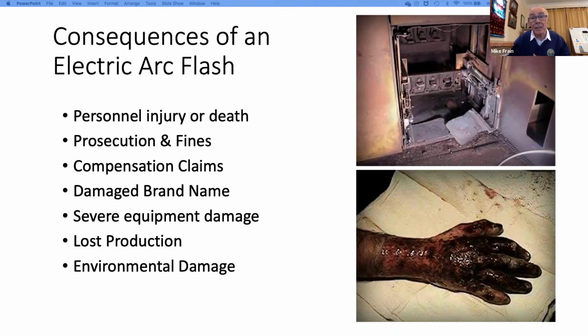Just recently, an electrical contractor here in the UK was fined £1 million plus costs for breaches of Section 2(1) of the Health and Safety at Work Act 1974. It followed burns to an electrician who was undertaking routine testing on low voltage equipment. Then there's another company, and this was only 2 days ago when I got to hear about it, and they were fined £660,000 under Section 3 of the same legislation. Again, arc flash on 415 volt equipment, low voltage equipment.